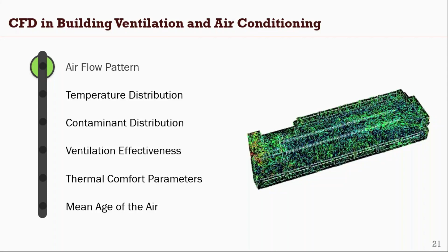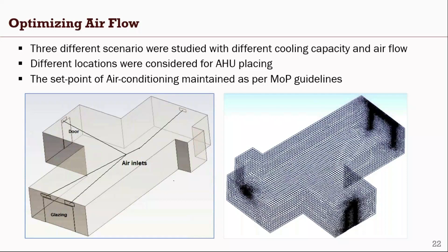Airflow pattern studies help optimize airflow. As you can see, this is a hall of a house. Three different scenarios were studied with different cooling capacity and airflow to optimize it. Different locations were considered for the AHU, and the set point of air conditioning maintained as per MOP guidelines, which is 24 degrees. These are the three cases showing temperature contours.